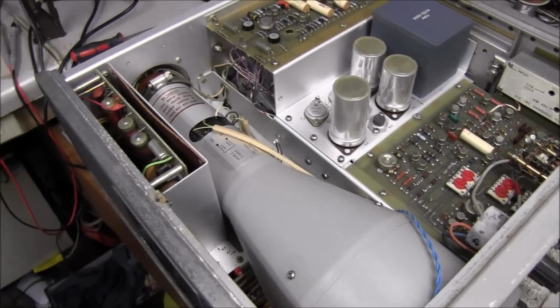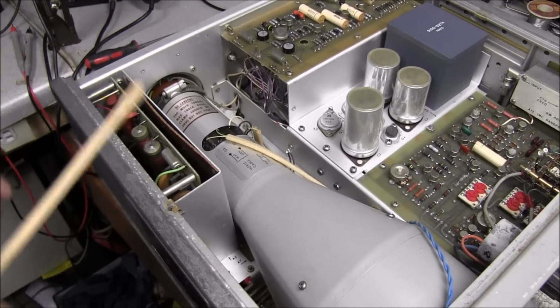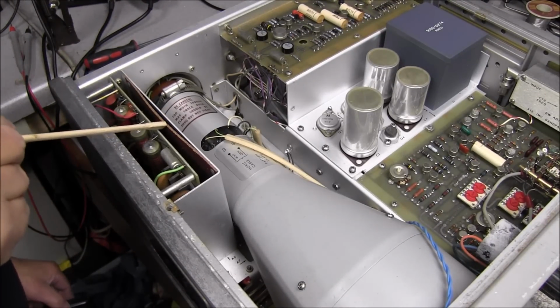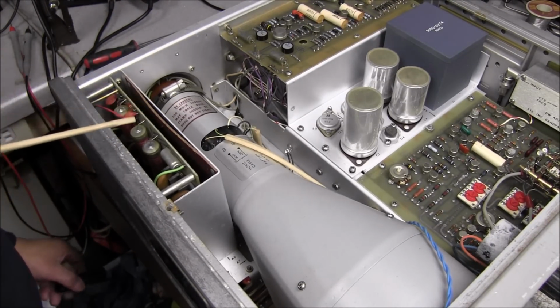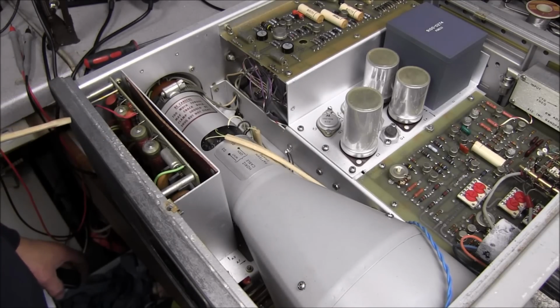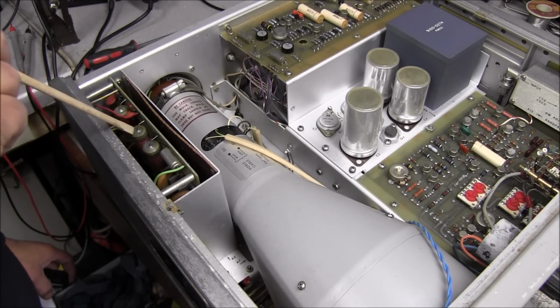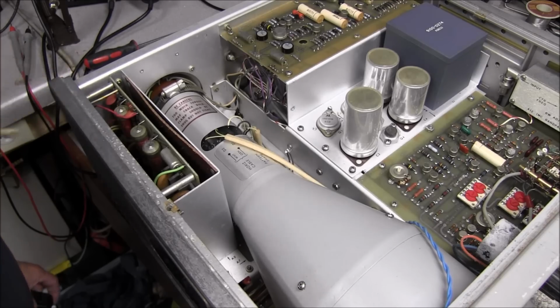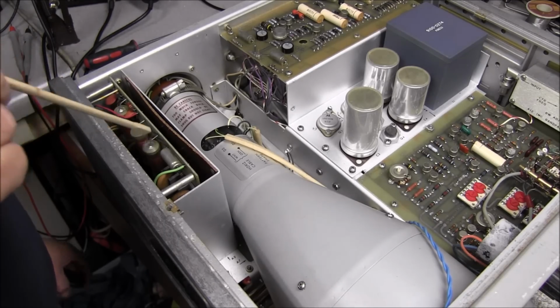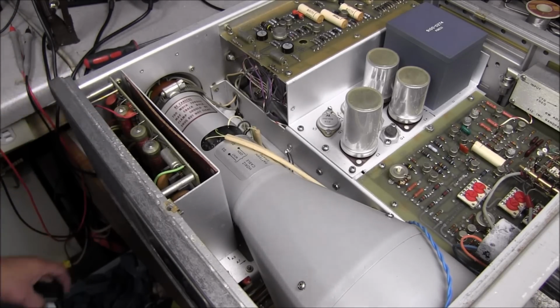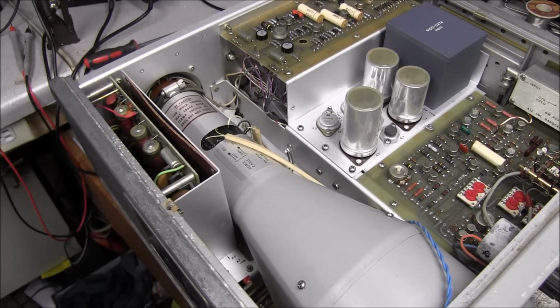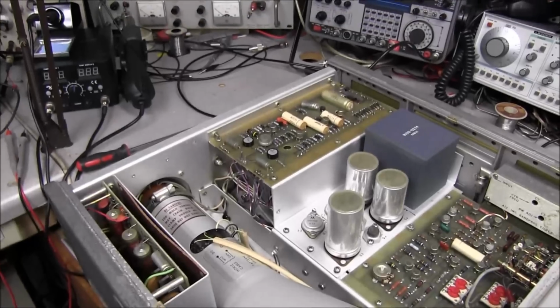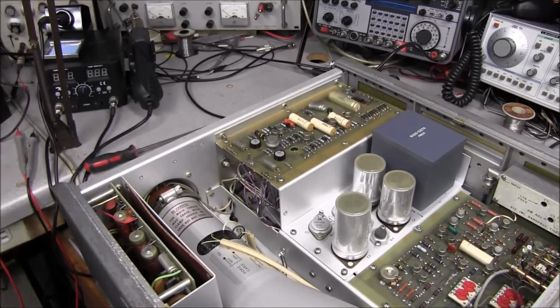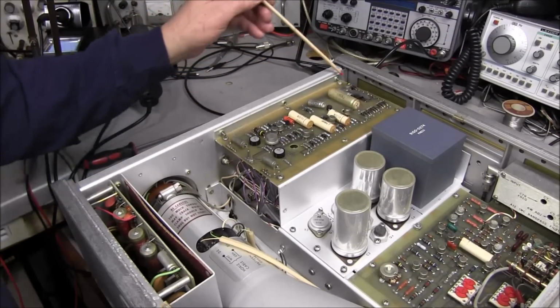And then over here on the side is the high voltage power supply board for the high voltage feeding the anode of the tube, and we can see a bunch of capacitors down in there. They're all small capacitors, no big capacitors, but we'll need to look at those and make sure that they're in good shape or replaced. And I think our first step is AC power in is over here on this side.